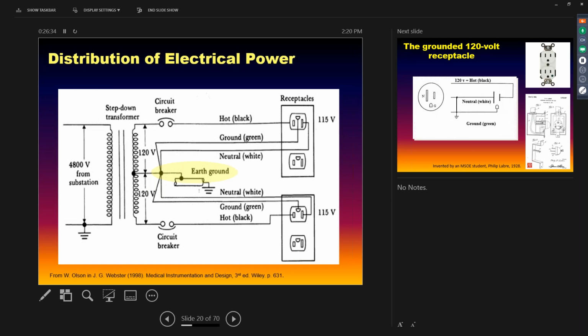That's why we refer to it as ground. In the UK they call it earth, because it's literally the earth. The point is that our 120 volts hot, the small blade, is electrically referenced to the physical earth, to dirt. That becomes a critical issue as we'll see going forward, but that's the fundamental nature of how this stuff is wired.